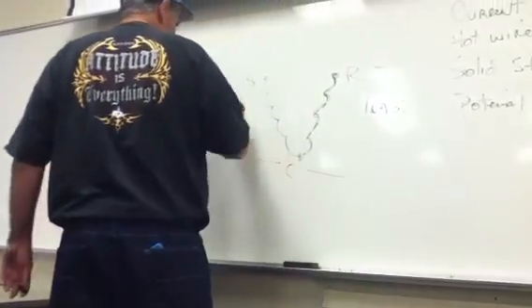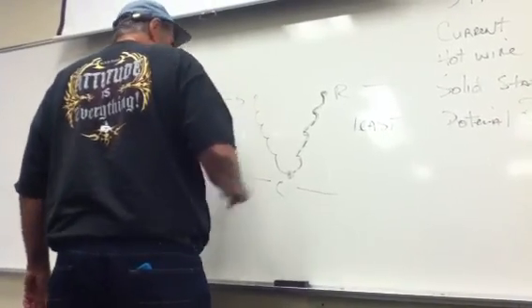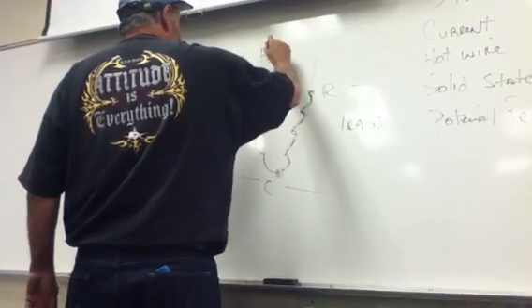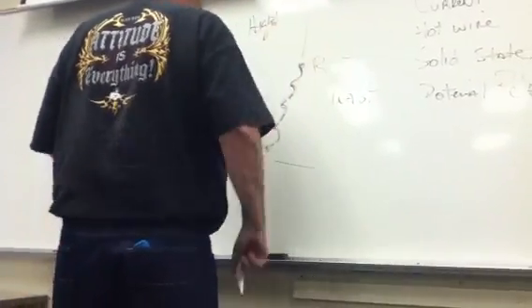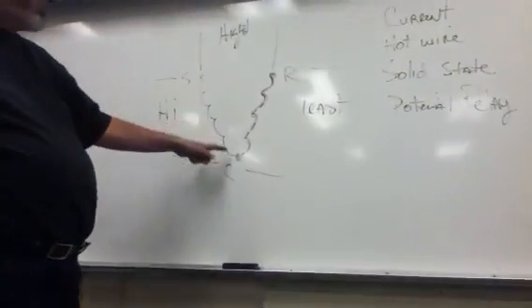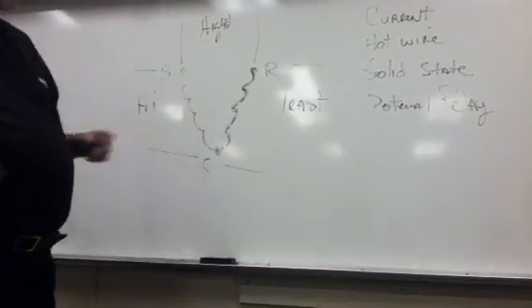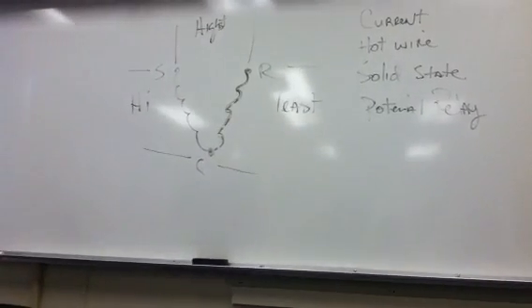The run winding from common to run is the least resistance. From common to start is the high. And the highest is from start to run because you're reading through both windings with your ohmmeter. So because the run winding is on all the time, they spend the money and put a decent sized wire in.